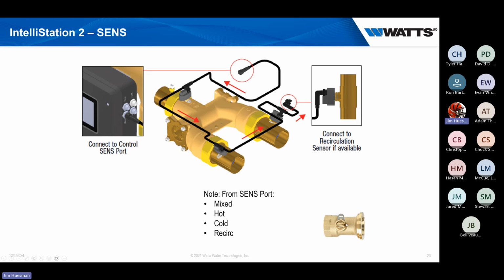On our service union, this is what it would look like if you bought it without any additional sensors, or if you want to add some things in. We're able to pull a C-clip, pull our plunger right out of there, insert our sensor right into there, and drop our C-clip back in. Then you're done, ready to go. We know we have the right depth, and we know our sensor is dropping into the actual moving water and not just sitting in a dead zone.